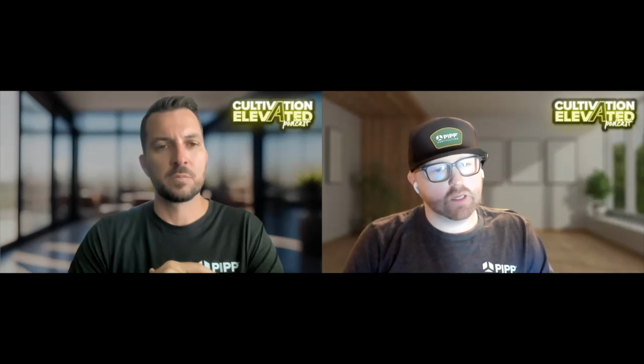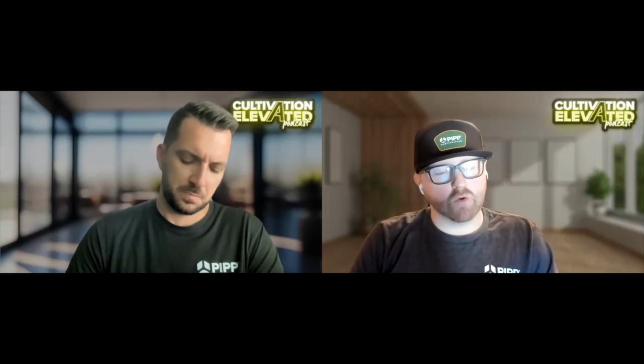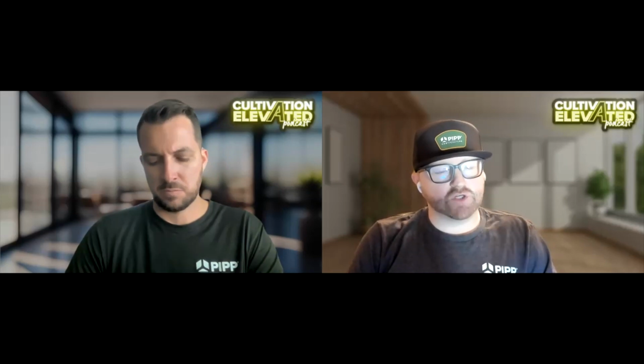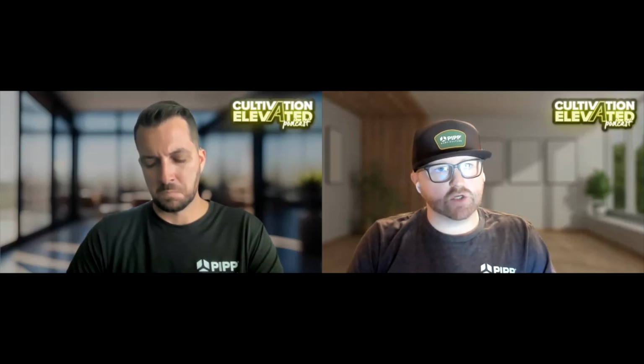And so yeah, I'll do one every 4 feet, and I'll record the average and the max typically out of that tool. One important thing is airflow is variable, right? There's no perfect laminar airflow in a grow room, so it can be turbulent. So the average is really useful because I will sit there and take a minimum of a 30-second recording when I take these airflow readings so that you have the ability to get a true average. Sometimes I'll let the recording go as long as a minute and a half, 90 seconds, if I'm having trouble getting a good reading. There's a lot of reasons why you might find a dead spot, but you've got to play around and find the location to get a good reading.